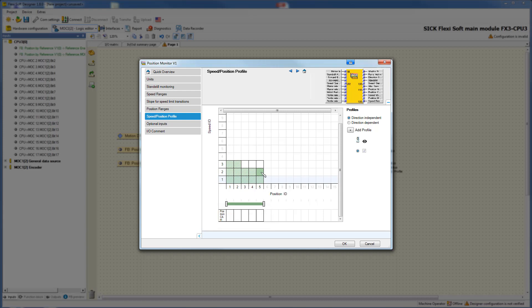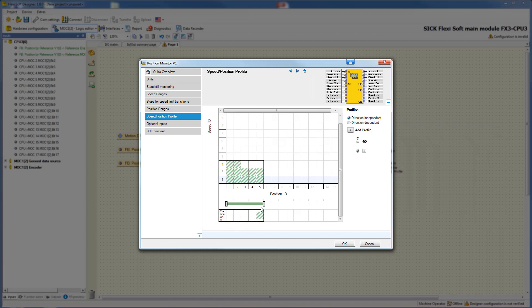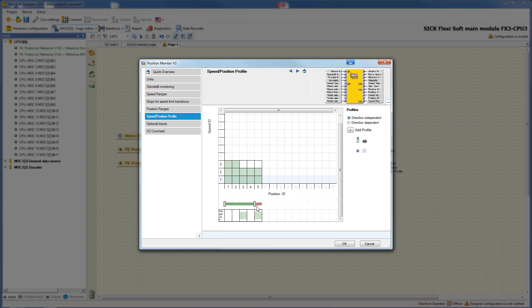In the configuration menu you can activate or deactivate the field for each position range by clicking. Activated fields are shown in green. If a machine enters a position range which is activated, the position cam output switches to 1. If a machine enters a position range for which the field is deactivated, the output position cam switches to 0. By moving the slider you have the possibility to activate or deactivate directions. In fields where the slider is green, it is allowed to move in both directions; where a red arrow is shown, it is only allowed to move in one direction.